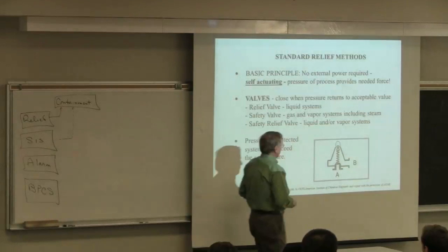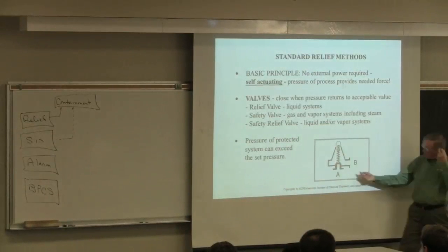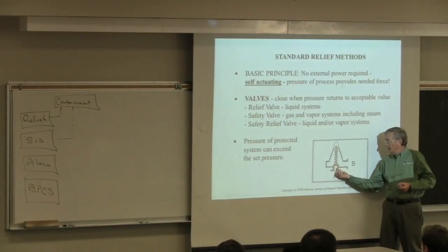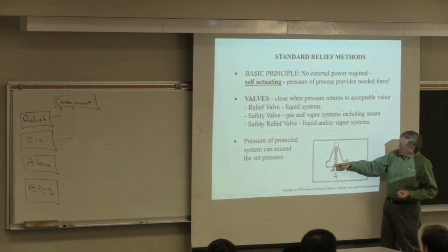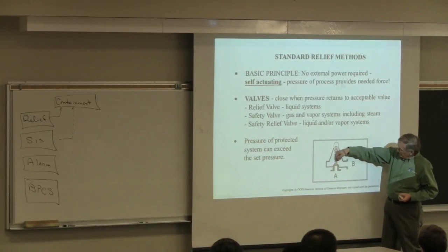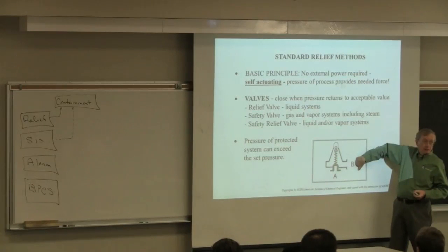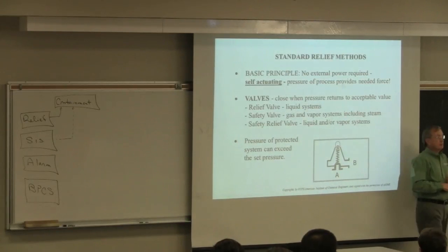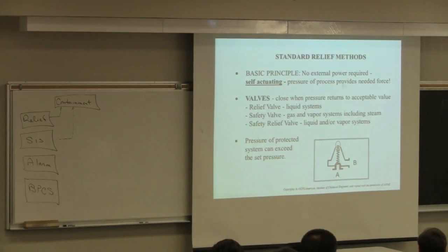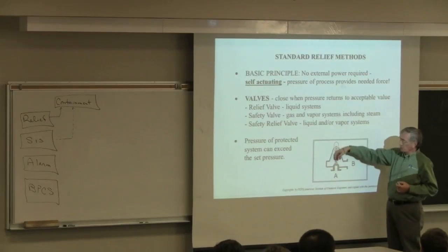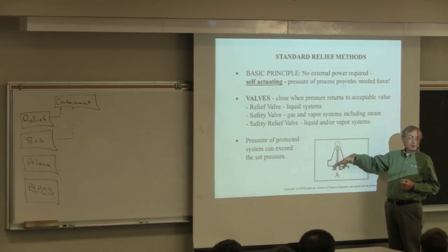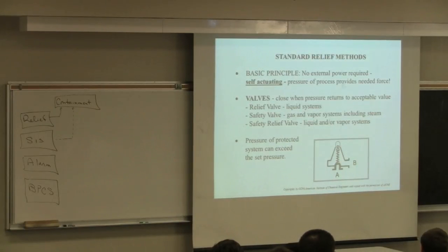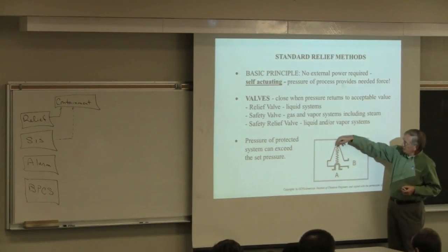To review: the safety valve works one way—pressure in the vessel builds up, pushes against a spring, and then relieves off. To adjust the spring pressure, there's a nut at the top that you can twist to set the pressure within a range. You need the proper spring first, then fine-tune with the nut. Safety valves can handle vapor, liquid, or two-phase flow.